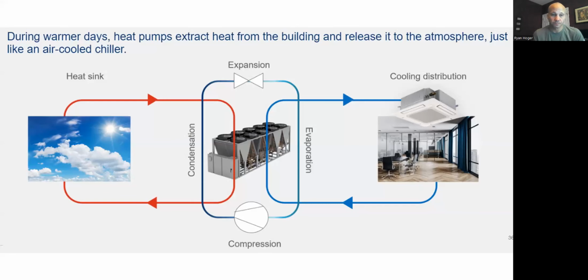It'll be more logical. All right, so I got the reversing valve inside here. So in the cooling season, I'm sending cold water out to the building. I'm dumping heat outside. In this case, it's an air-cooled machine, right? I got my evaporator coil inside the chiller, my condenser coil inside the chiller, my expansion device like a TXV, or in a chiller probably an EXV, an electronically controlled TXV, and I have my compressor on here, right?